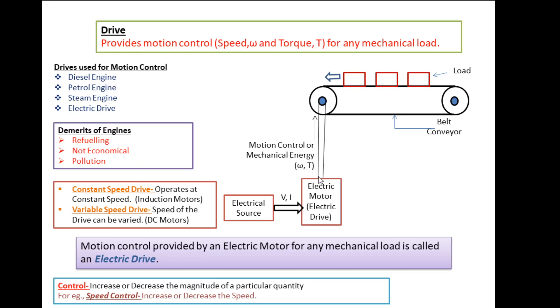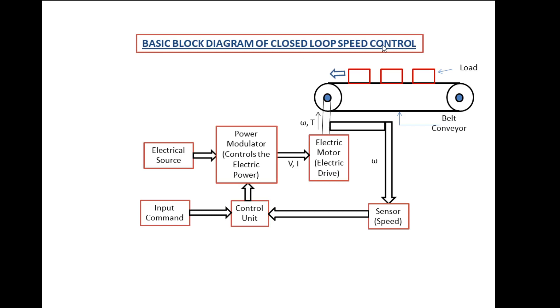For speed control, we need a closed-loop system. In the basic block diagram of a closed-loop speed control system, electrical input energy is given to a power modulator. The power modulator has two functions: first, it can change the nature of the electrical signal — from AC to DC or DC to AC as required. Second, it can control the electric power — increasing or decreasing the voltage or current as per the load requirement. The output of the power modulator is given to the electric motor, which converts electrical energy into mechanical energy in the form of speed and torque for the belt conveyor.